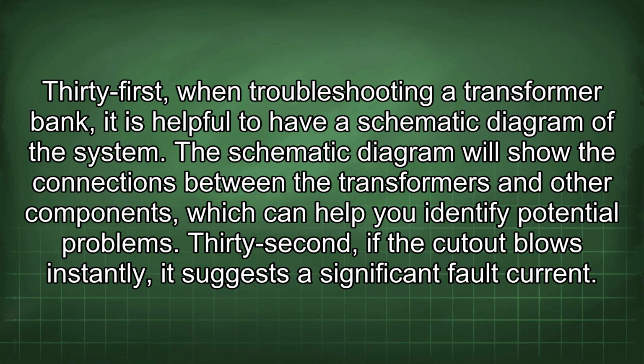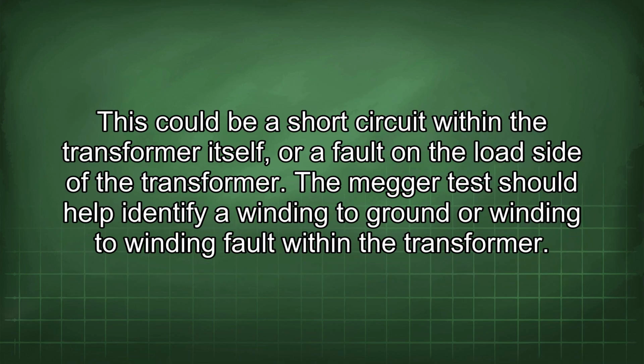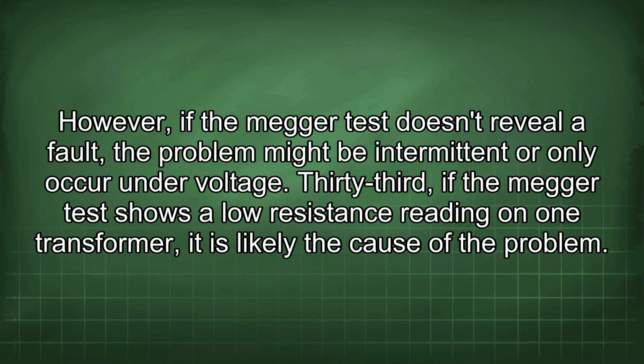32nd, if the cutout blows instantly, it suggests a significant fault current. This could be a short circuit within the transformer itself, or a fault on the load side of the transformer. The megger test should help identify a winding to ground or winding to winding fault within the transformer. However, if the megger test doesn't reveal a fault, the problem might be intermittent or only occur under voltage.